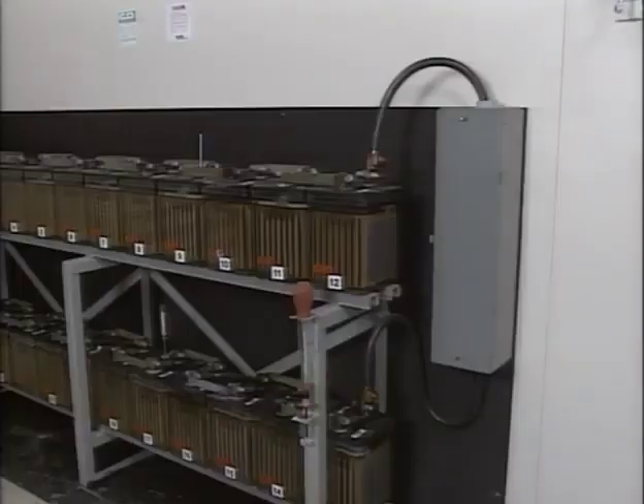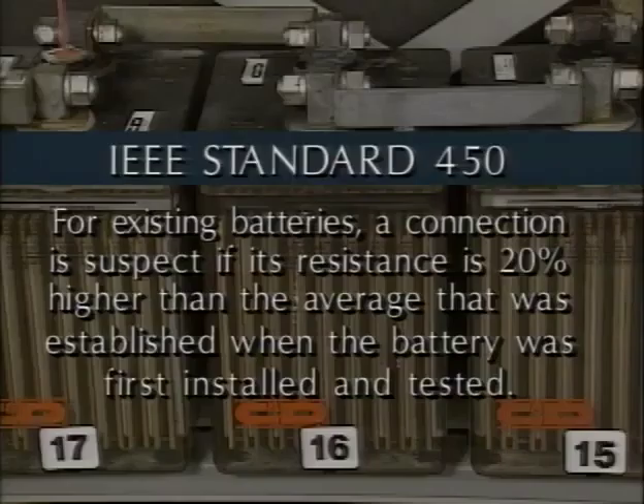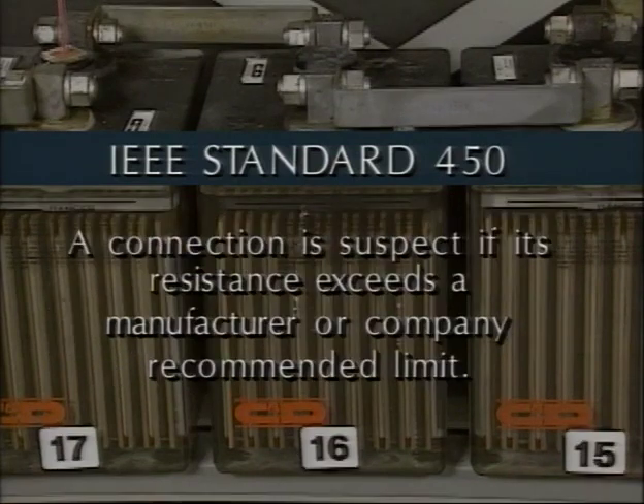An example of a type of connection is all intercell connections. Another type is all inter-tier connections. For existing batteries, a connection is suspect if its resistance is 20% higher than the average that was established when the battery was first installed and tested. Or a connection is suspect if its resistance exceeds a manufacturer or company recommended limit.